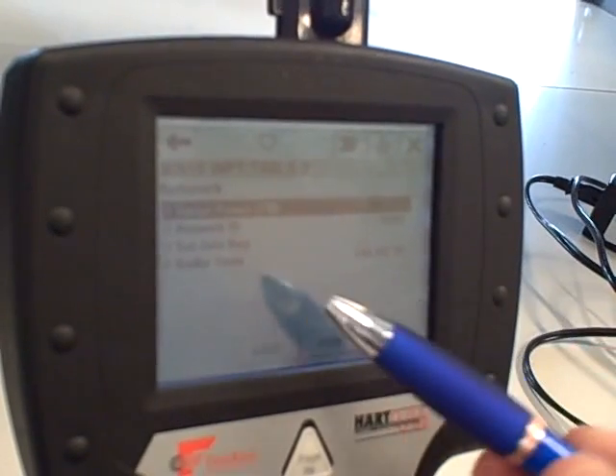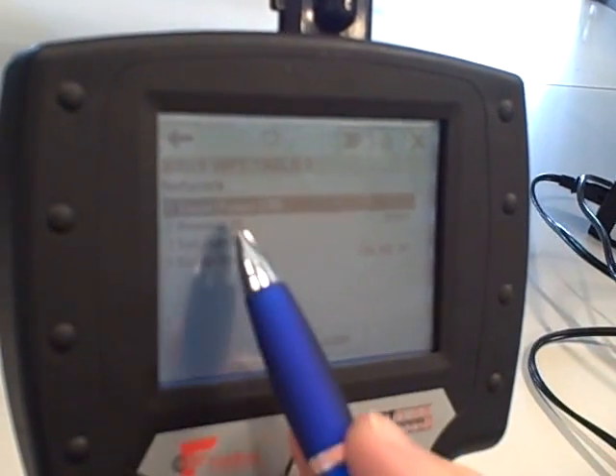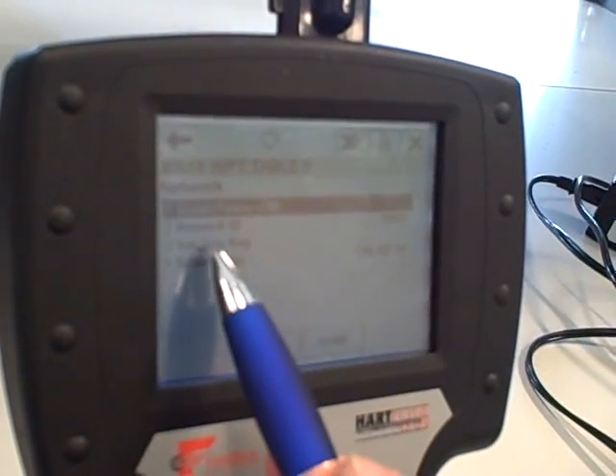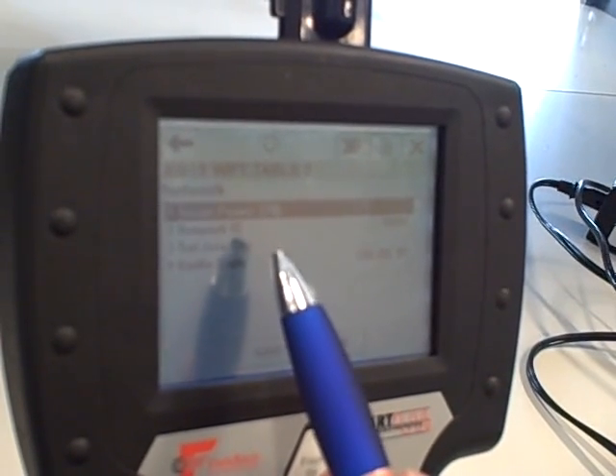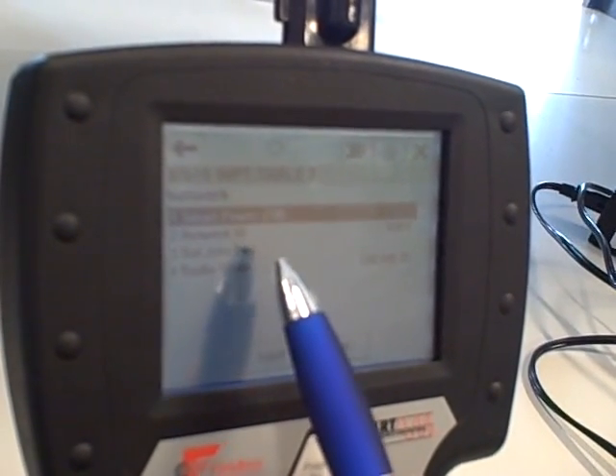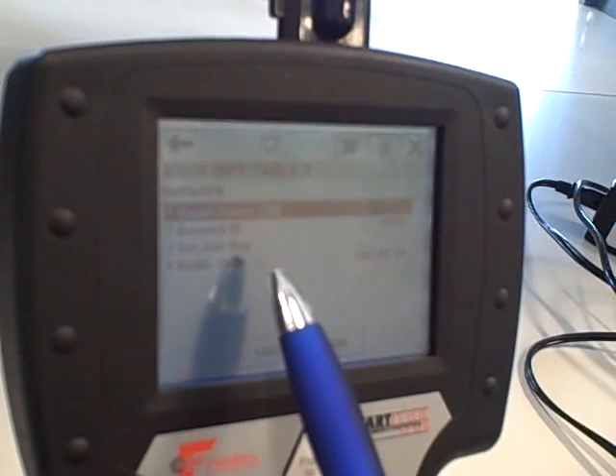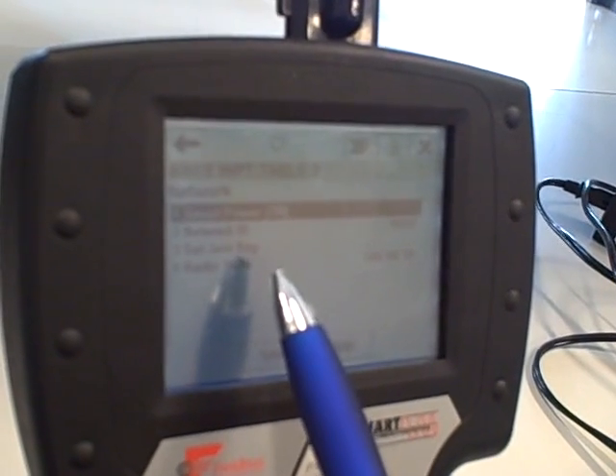We see here a Network option. If I navigate under Network, we see a couple of things: a network ID and join key. These are the two parameters that must be programmed into the device for it to join the wireless network. This is how Rosemount implements security with their wireless HART devices.